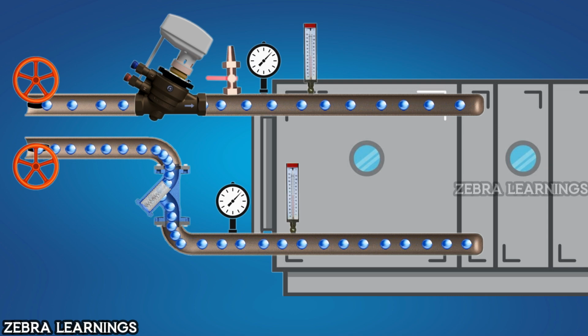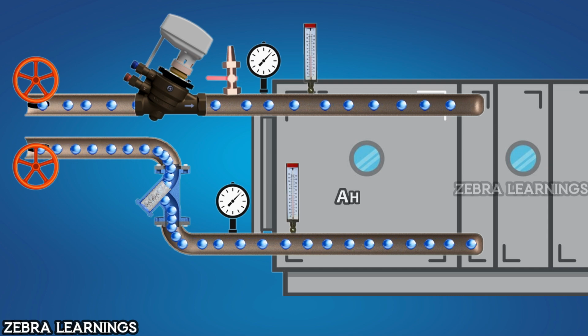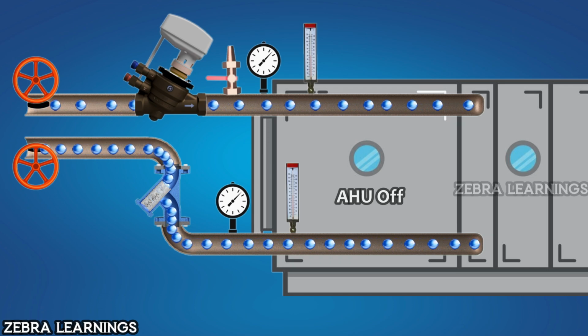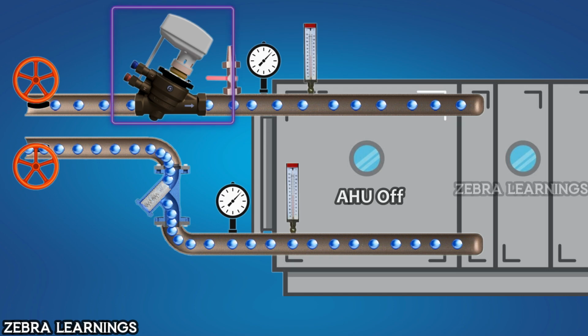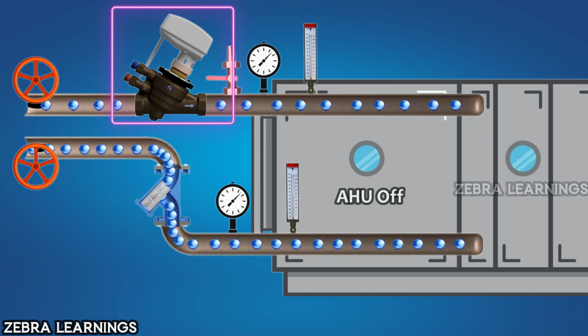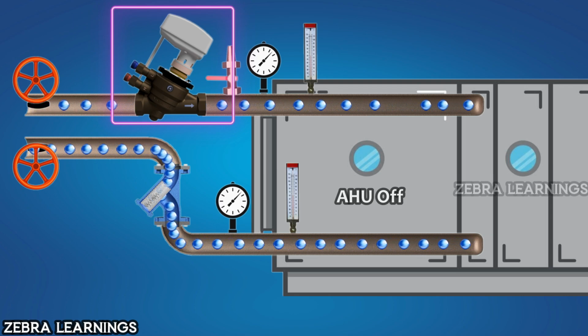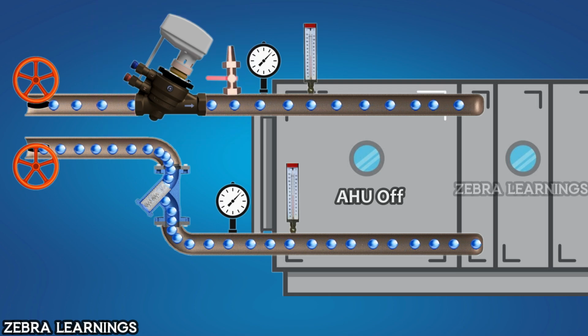To remove this strainer, we first need to turn off the AHU. Once the AHU is off, the PICV located on the return line will close. This will stop the water flow in the pipeline. After that, close the valve on the return line. Then, close the valve on the supply line. Now, slowly open the drain port on the strainer and remove all the water in the pipeline.